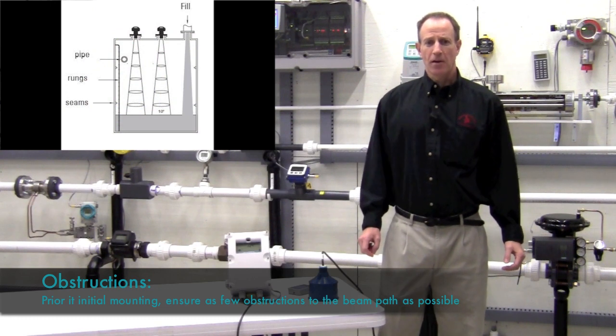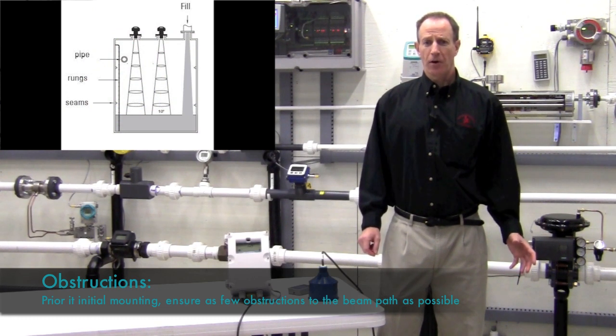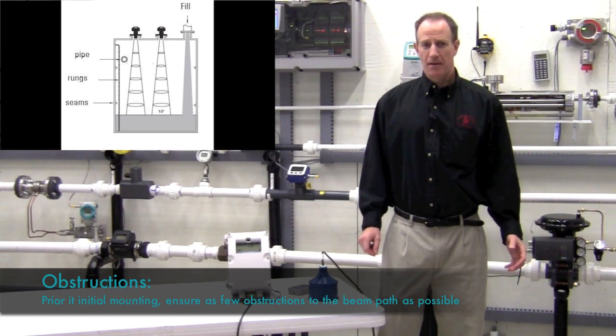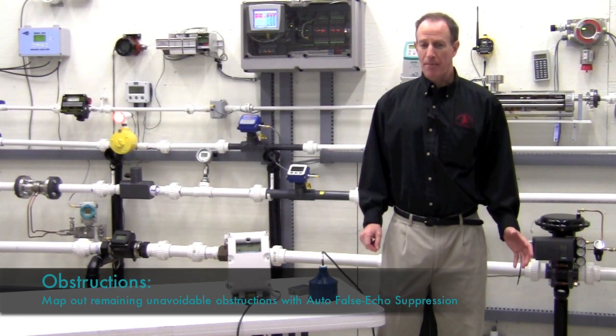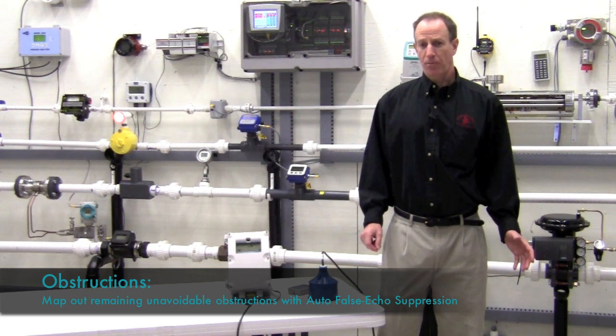Obstructions inside the vessel may cause false reflections. Before mounting the sensor, make sure there aren't any obstructions in the beam path. If you cannot get away from all the obstructions, the Hydro-Ranger may be able to map them out with auto false echo suppression function.